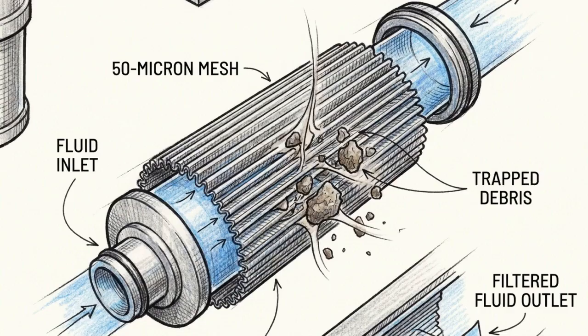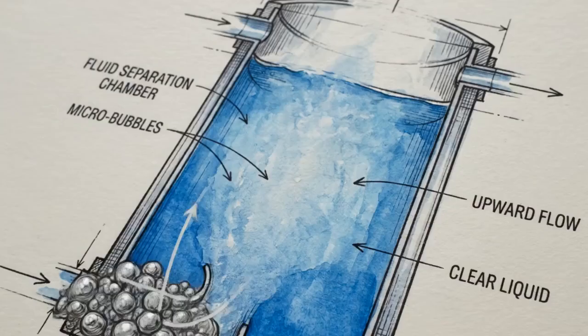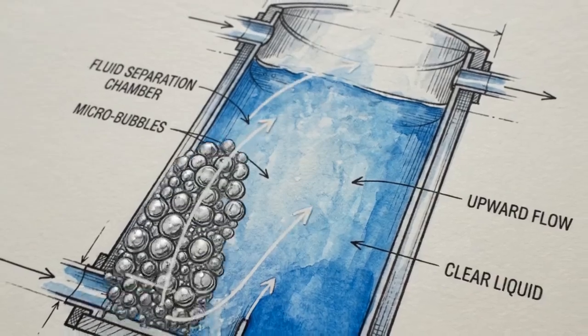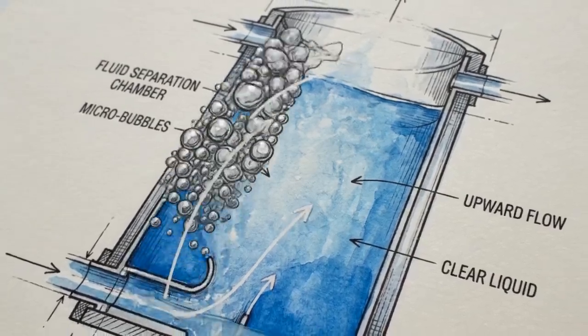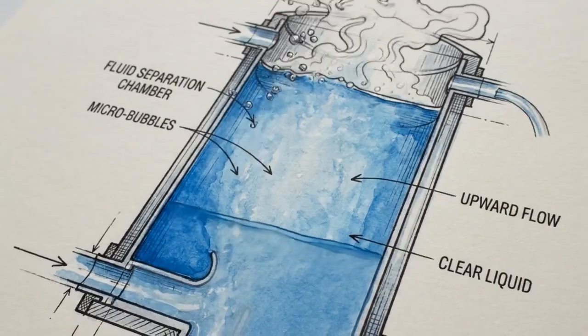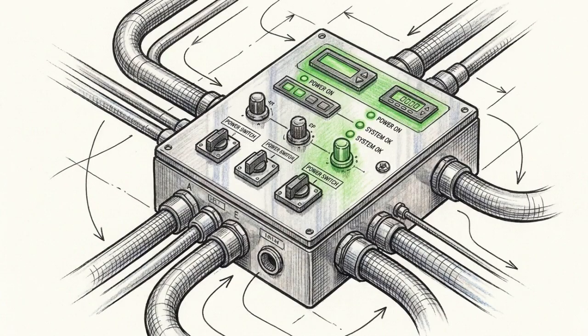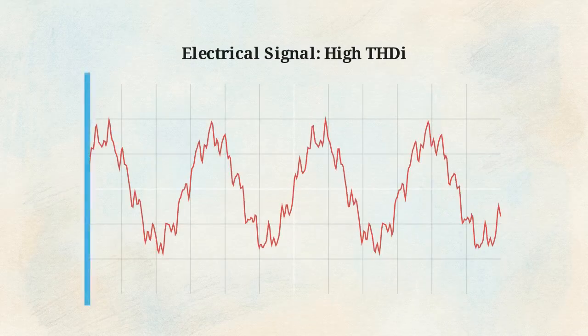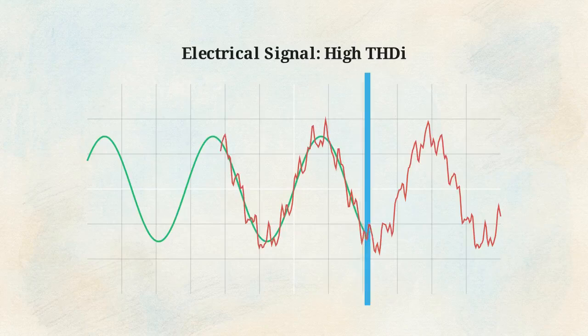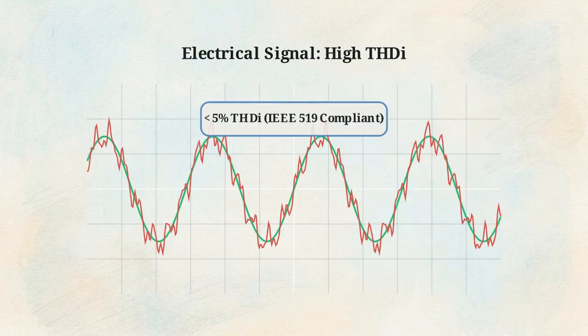Fluid quality is heavily guarded. Full-flow 50-micron filters protect the fine fin pitches inside the cold plates, while integrated microbubble air separators absorb the rapid fluid expansion that occurs when GPUs spike to full load. The electrical demands are equally controlled. The pumps use active front-end variable frequency drives to keep total harmonic distortion under 5% at all loads, preventing high-frequency feedback from disrupting the emergency generator buses.